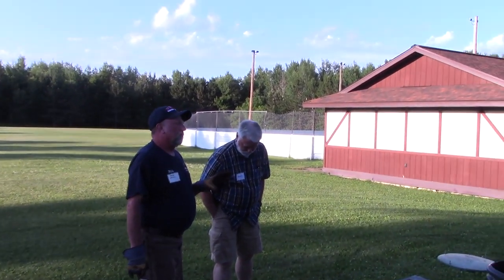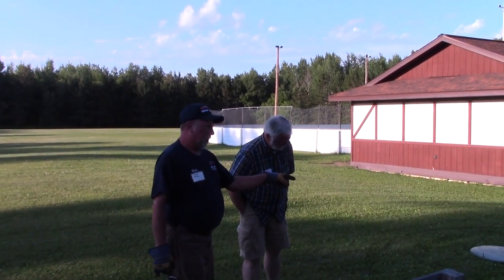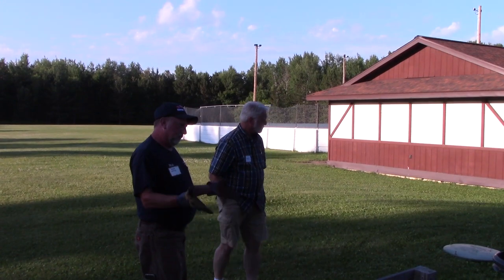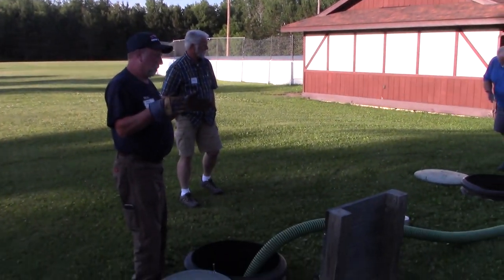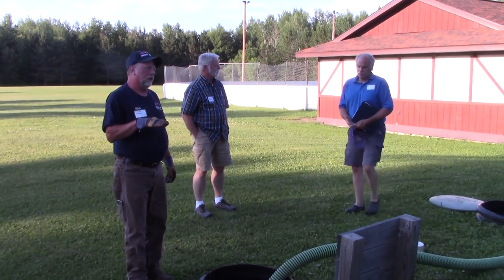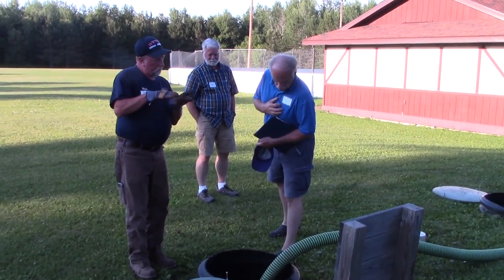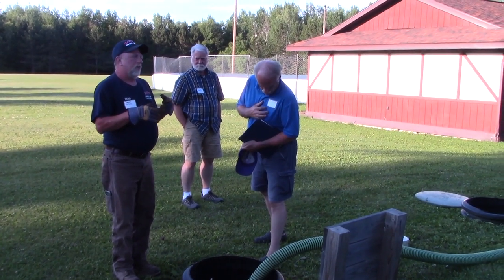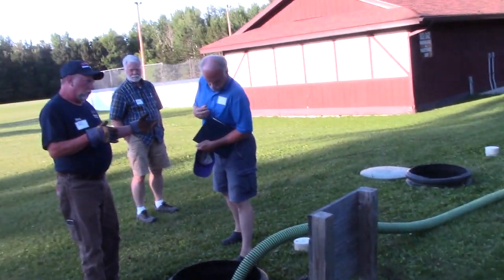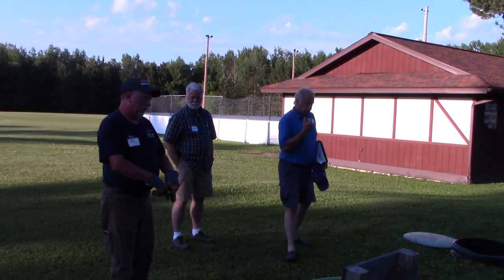A third. It goes over there naturally. All of the wastewater from the building comes into this tank first. It has to fill to an operating level, which is approximately 3.5 feet. It varies from tank to tank, but once it fills to that level, every gallon of water that's used from that point on, a gallon is displaced into this side.